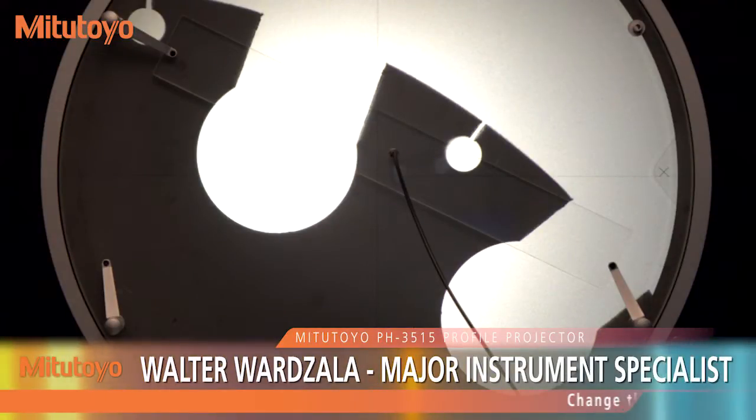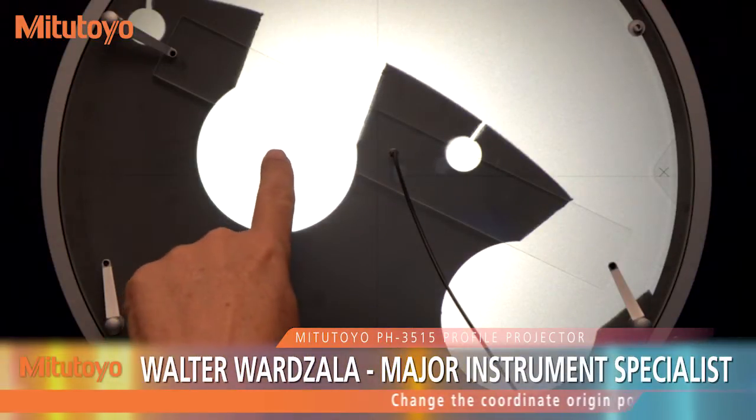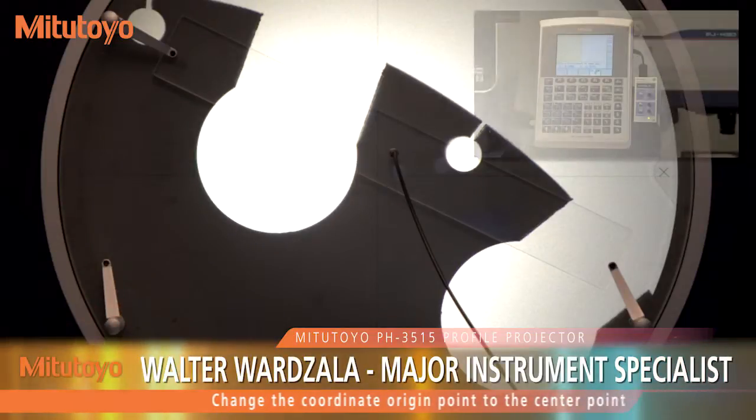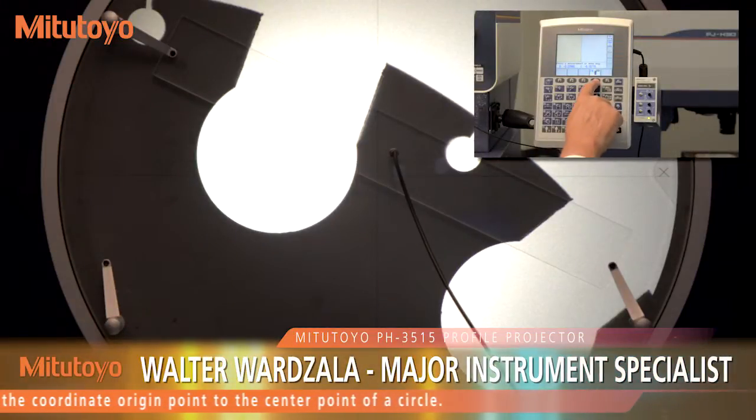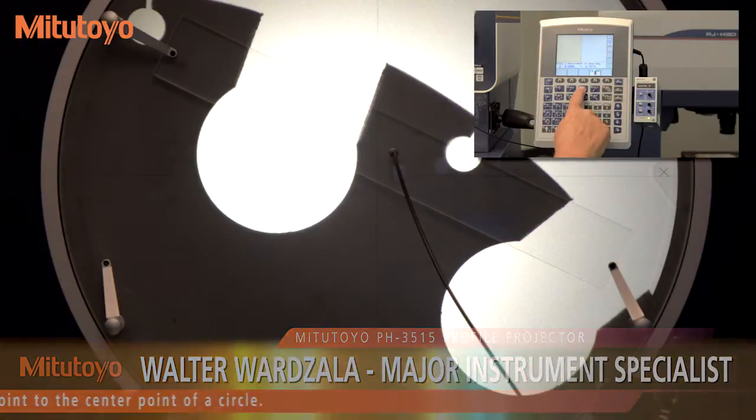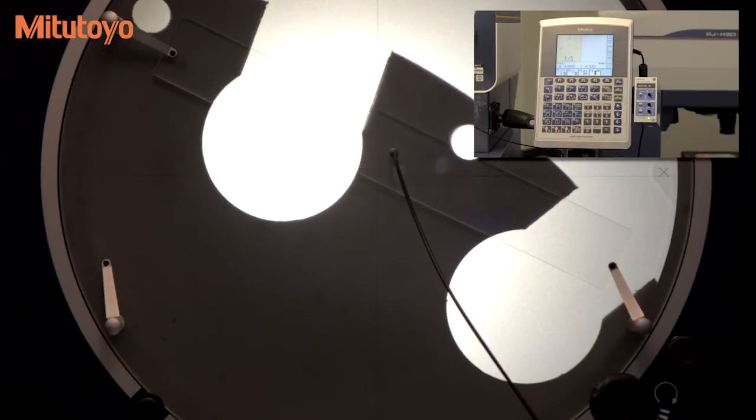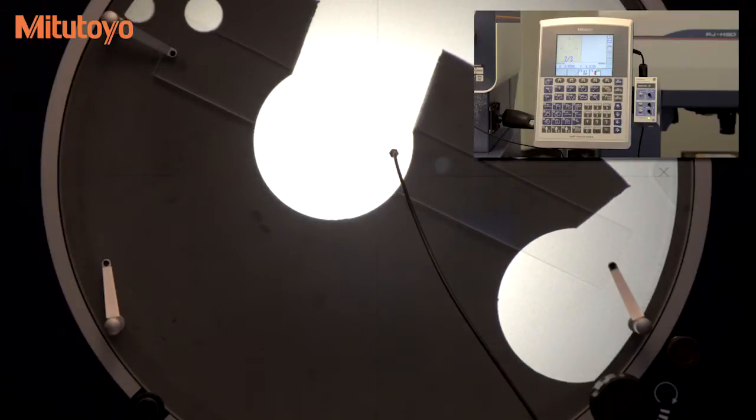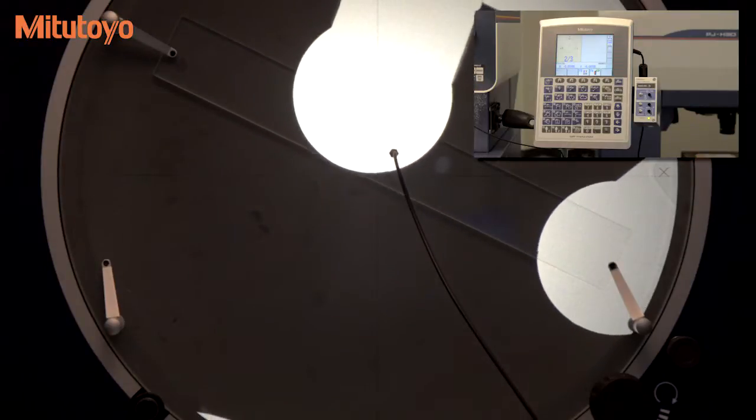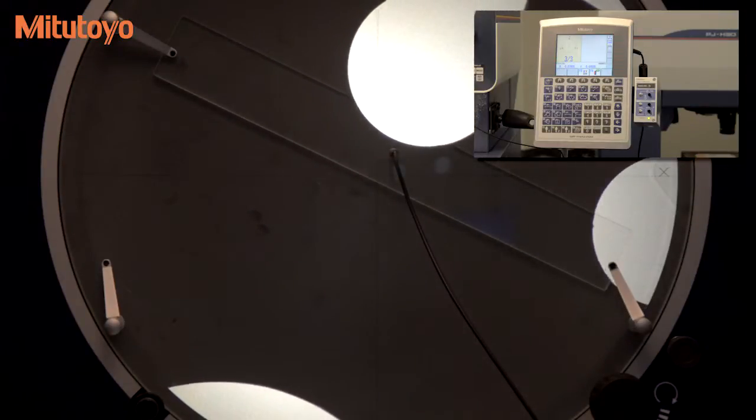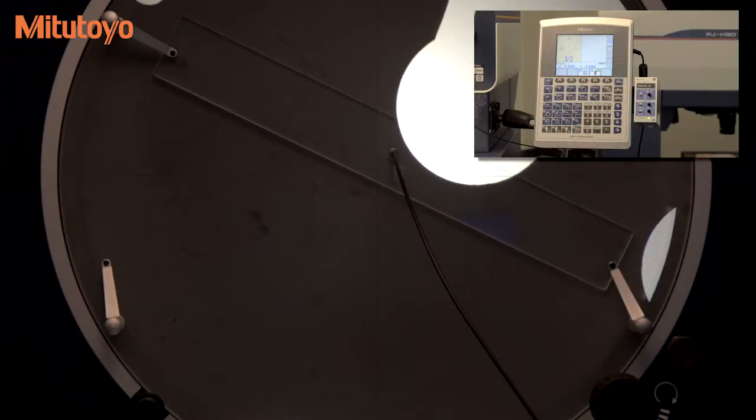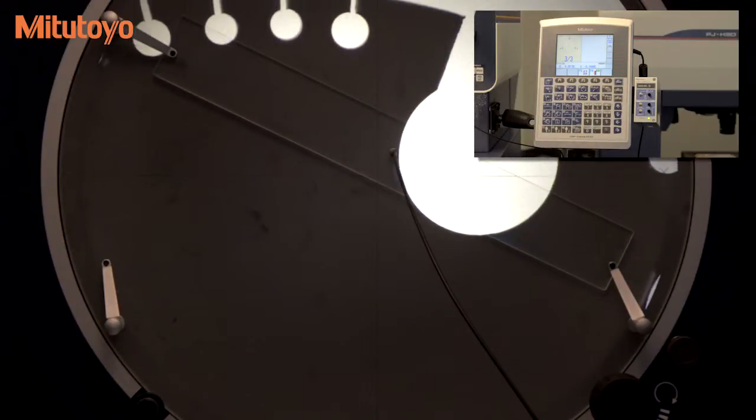To align a coordinate system to your part, rather than having to align the part to the coordinate system, use the basic commands to find the point or angle or line that you want to use to align your new origin. Here we find the center of a circle to use as our new origin. Select the method to use to move the origin, just simple X and Y position in this example.